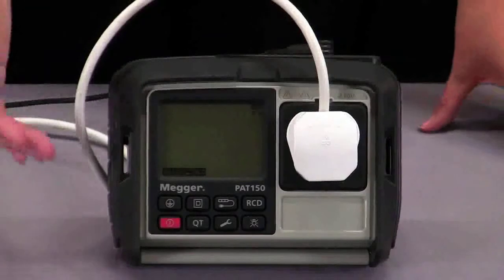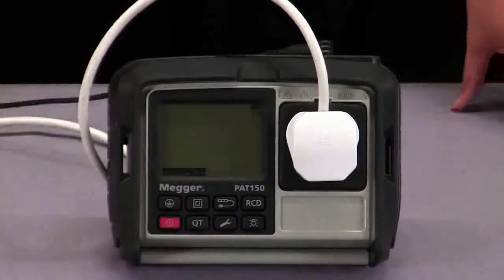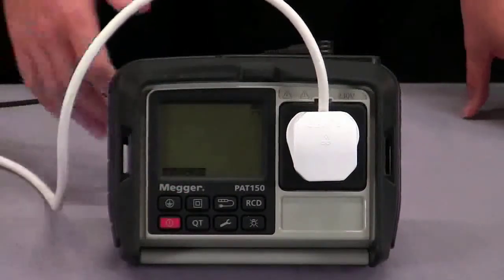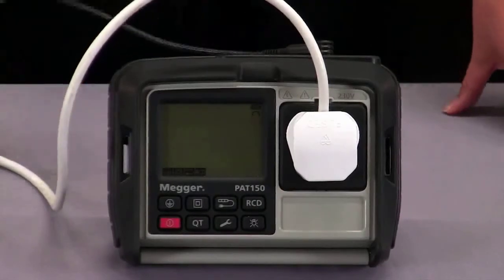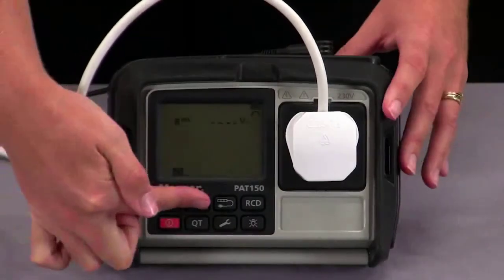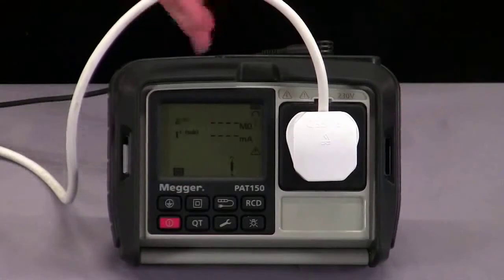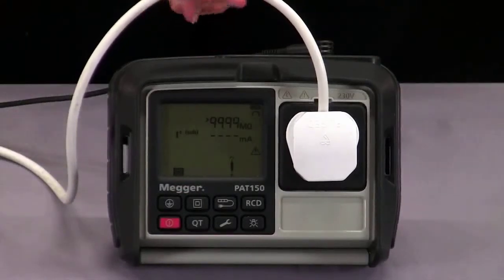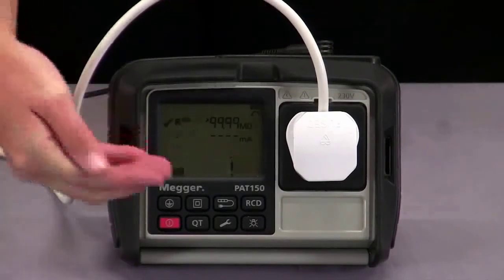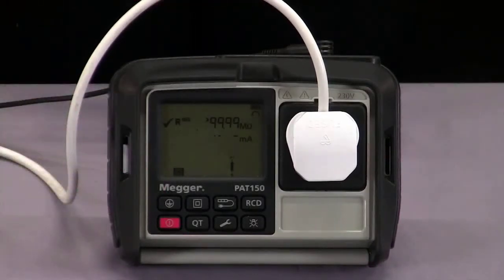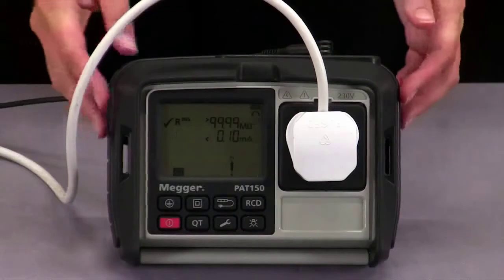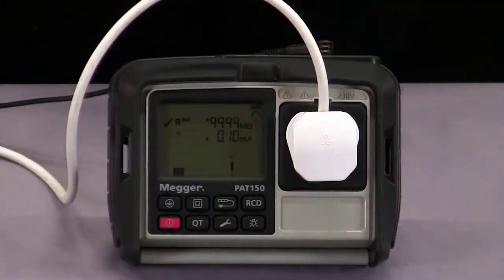I shall now demonstrate the Class 2 automated sequence. I've got my fan plugged in here and my lead connected to the exposed metalwork. I can press the Class 2 button, which will start the test. I've selected 500 volts, but 250 volts can be selected for IT equipment. It will then move on to my substitute leakage test, and as before, pass or fail will be indicated on the right hand side by a tick or a cross.